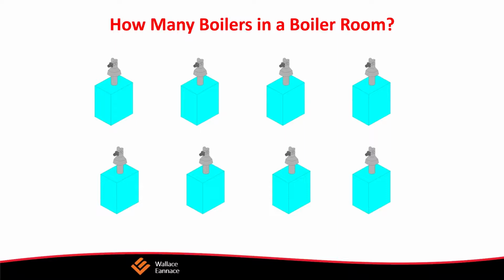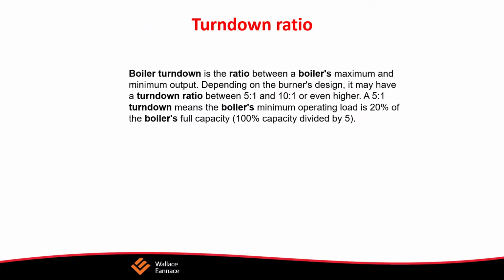Cooling mode is only about 10% of the time. To design around the cooling system is actually backward. Out of 8,000 hours of heating, design conditions occur less than 100 hours. That means 99.9% of the time, the building can be heated with less boiler or less radiation. So how do we implement that concept into efficient selections of equipment? Well, you could put in smaller boilers, or you could put in less radiation, or we could lower the water temperatures. How does that work out?